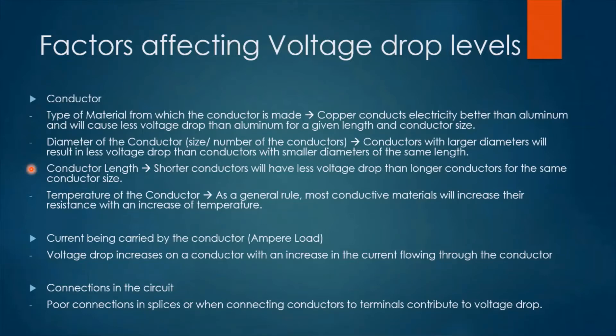The temperature of a conductor can also affect the voltage drop level. The higher the temperature of a conductor, the higher the resistance, which means an increase in voltage drop. The second main factor that can affect voltage drop is the current carried by the conductor — voltage drop increases with the increase of current flowing through the conductor.